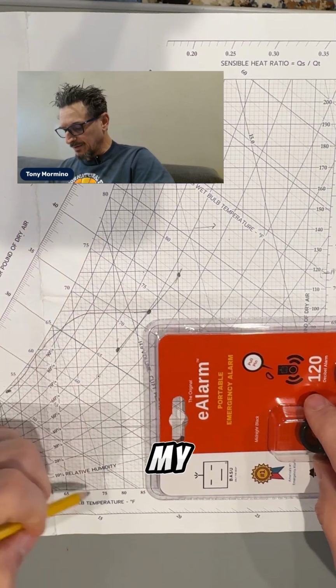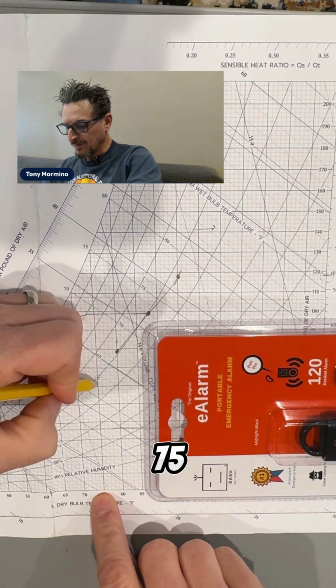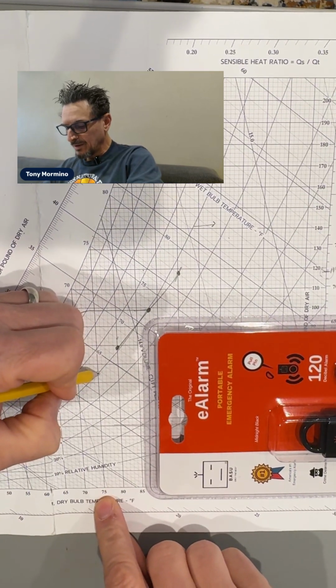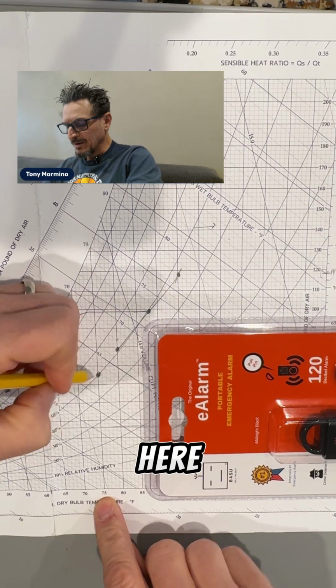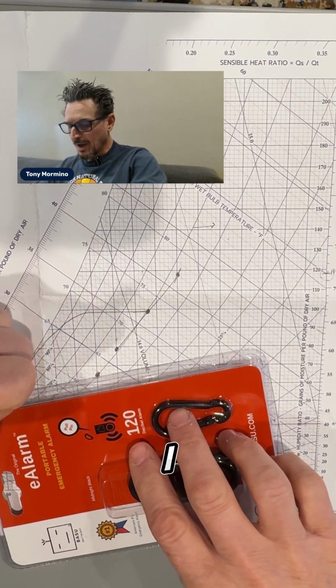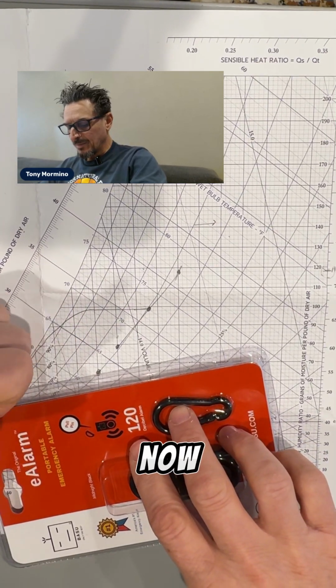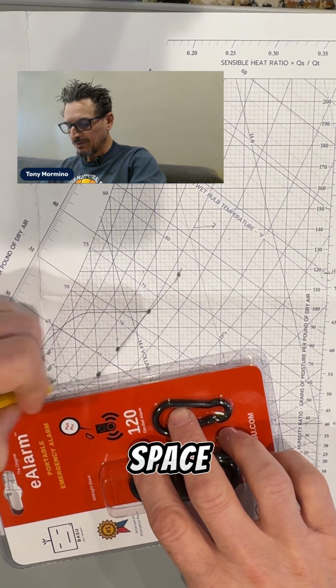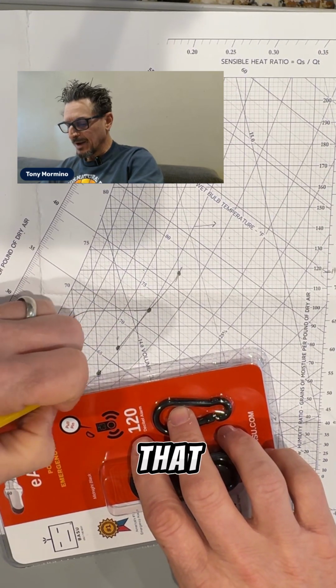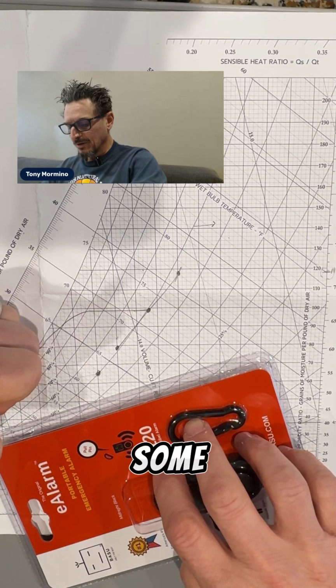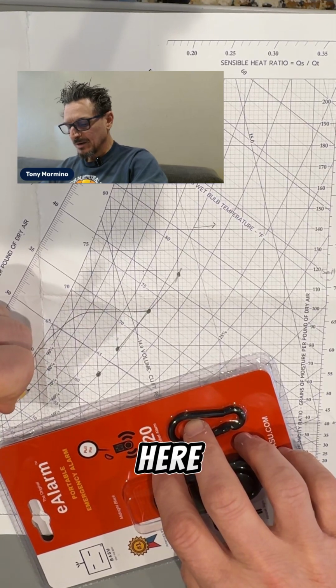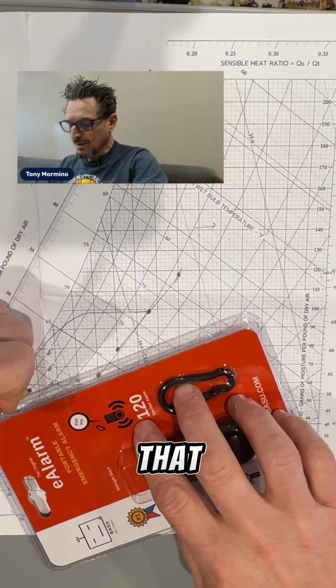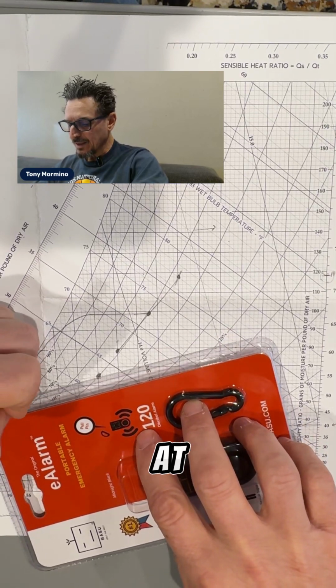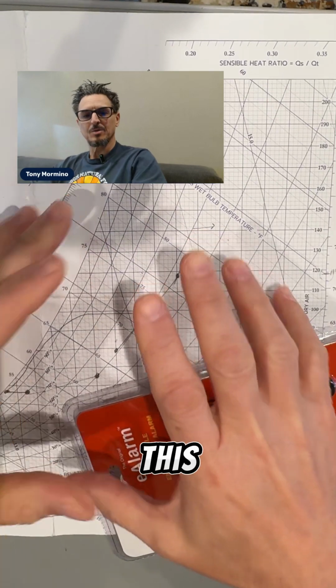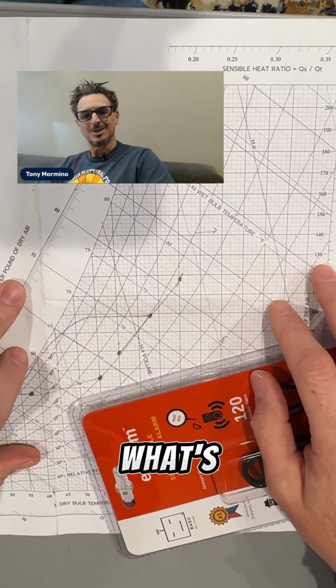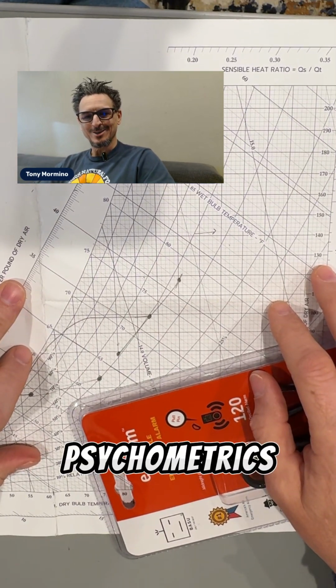And if my design objective is 75, 50%, I would plot that here. So I know I need to get from here to here. Now, depending on the sensible heat ratio of the space, if it's designed perfectly, that might happen. Or I might need to have some reheat, which would go from here to here to hit that sensible heat ratio, whatever it is at that time. So you can see by doing this process, you can fully understand what's happening using psychrometrics.